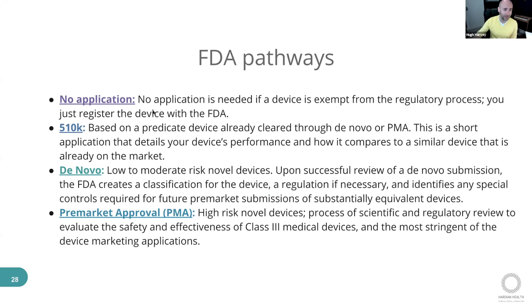The most common is the 510k route. This is where you say, look, there's someone already on market with a largely similar device. Here's my studies to show that my device is pretty much exactly the same as that device. Can I get approval based on being like that? It's a predicate device system.